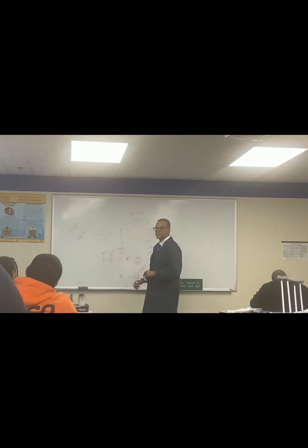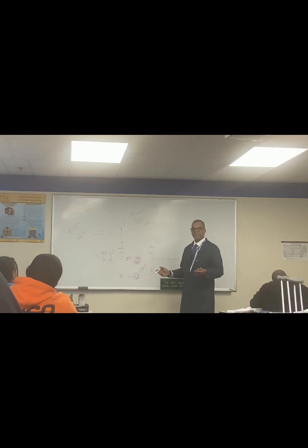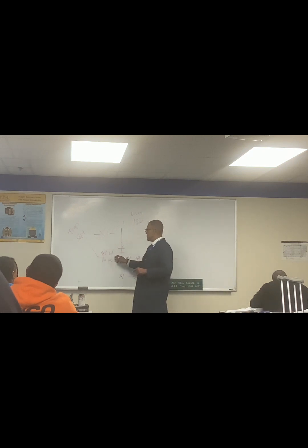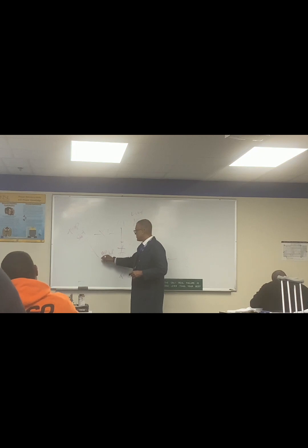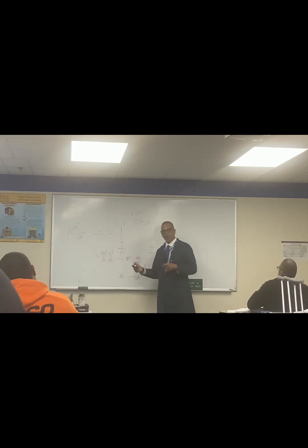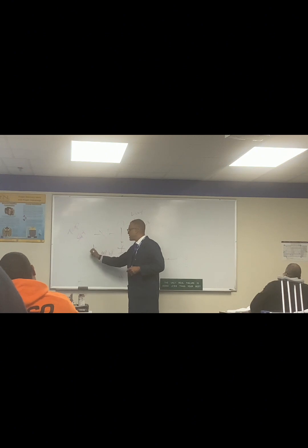Say two pressure switches. Why? Because these are in series with the 24 volts to the contactor, meaning if pressure is too high, the switch opens. If pressure is too low, the switch opens. When the switch opens, this wire coming from the stat represents what color?